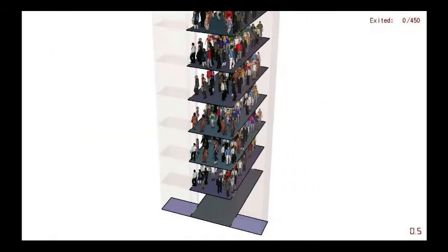Here's a snapshot at the beginning of a test model showing full elevator lobbies with two elevators. There's an incident on the second or third floor, and the elevators have been set to a priority queue — they'll clear out that floor, then the floors above and below, and then finish the rest of the model. This demonstrates that the feature is working, and it's all in the current 2011 release of Pathfinder.